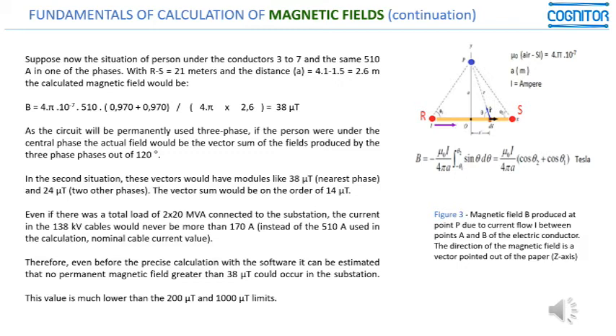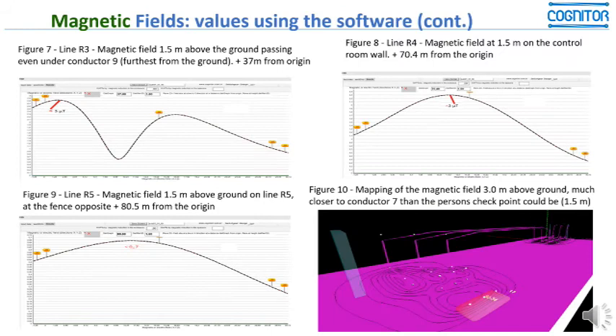Even if there was a total load of 2 times 20 MVA connected to the station, the current in the 138 kV cables would never be more than 170 amps. You see, we are doing the calculations with 510 amps, three times more, so we are calculating values which are much higher than the actual fields.